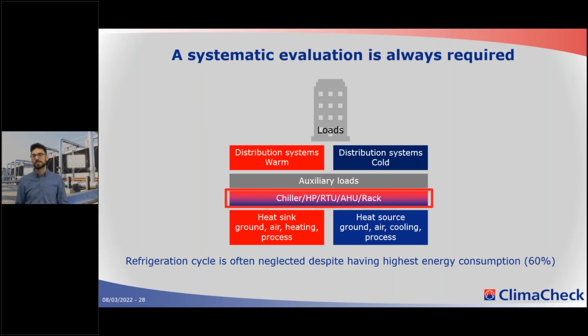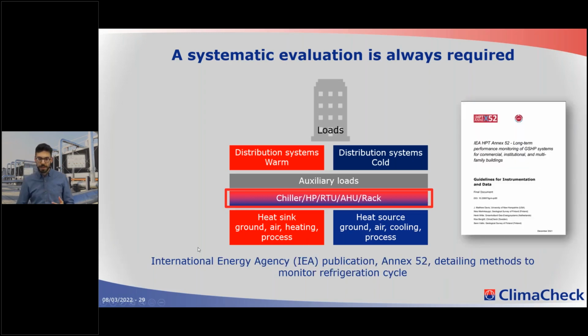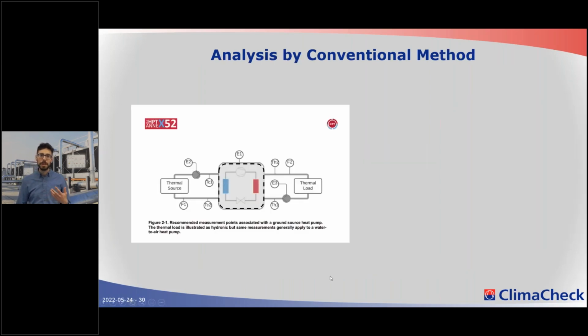And that is why we want to focus here, because most energy consumption is happening in the chiller, heat pump, the refrigeration cycle. So how do we measure that? We have our method, which has been published also in the International Energy Agency, Annex 52. We have the link for this at the end of the webinar. Now, the conventional system to measure the refrigeration cycle is basically to consider it as a black box. We're looking at the temperatures in and out of the system, the pumps, the fans, but the actual refrigeration cycle is taken to be a black box.